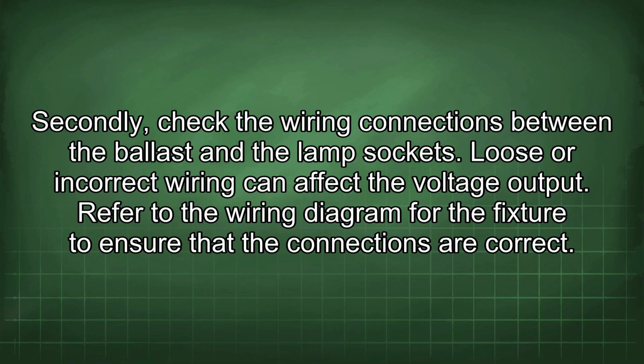Secondly, check the wiring connections between the ballast and the lamp sockets. Loose or incorrect wiring can affect the voltage output. Refer to the wiring diagram for the fixture to ensure that the connections are correct.